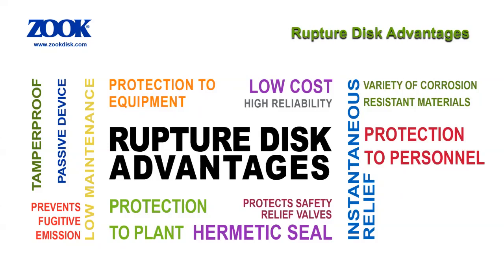Rupture discs are passive devices with no moving parts. They are extremely fast opening, typically going from closed to fully open in less than 3 milliseconds. Rupture discs provide a leak-tight seal and are available in a wide variety of corrosion-resistant materials. Since there are no moving parts, rupture discs are virtually zero maintenance devices with very high reliability. They are time-tested safety products. Therefore, rupture discs are a very effective low-cost solution to a pressure relief requirement.